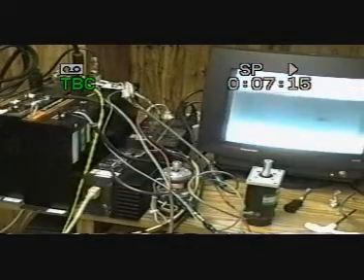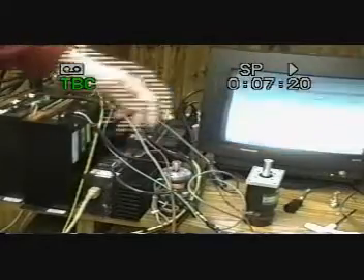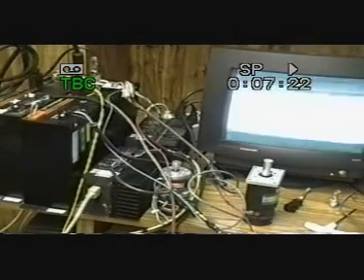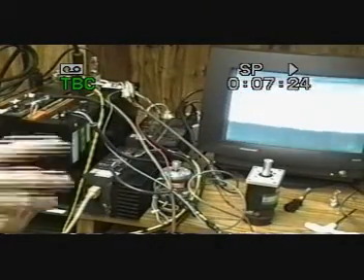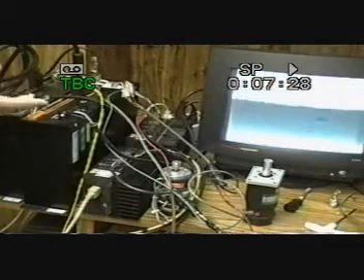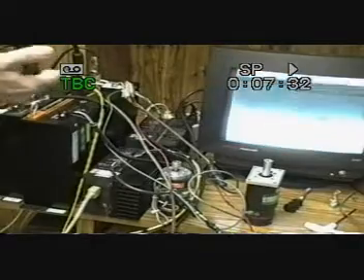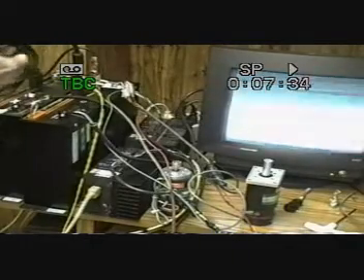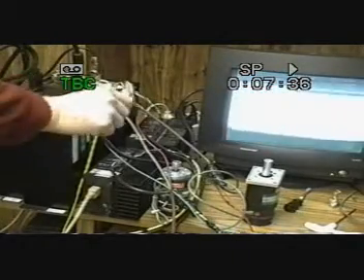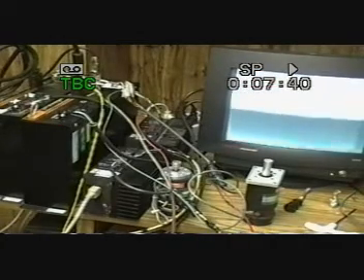It's a marginal speed. What we'll find out is when we slow that down, we do indeed get an encoder 2 fault. That had nothing to do with the speed. It was just that the signal pulse coming in degraded. As you saw with the prior demonstration, with a fully shielded cable and a strong signal, I could run that at finger speed and it would follow and it would never fault out.